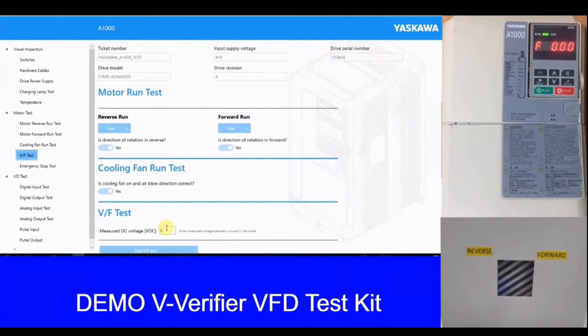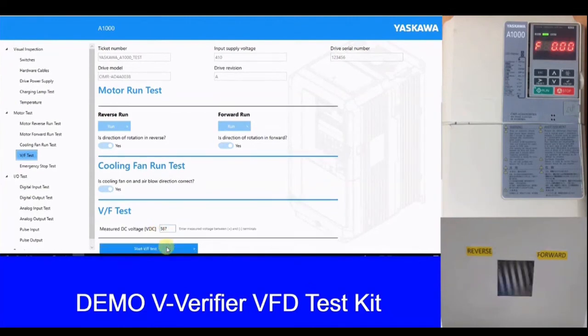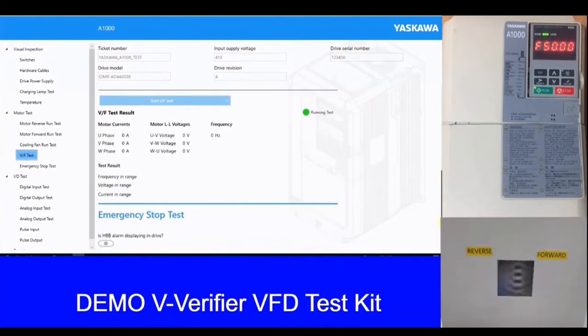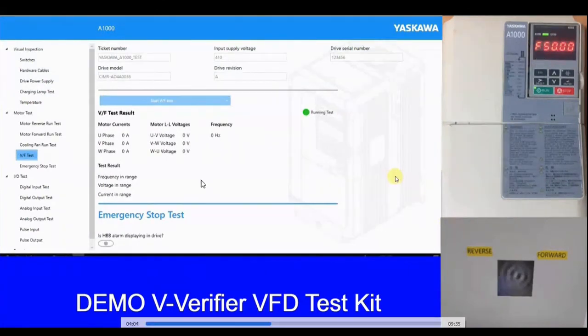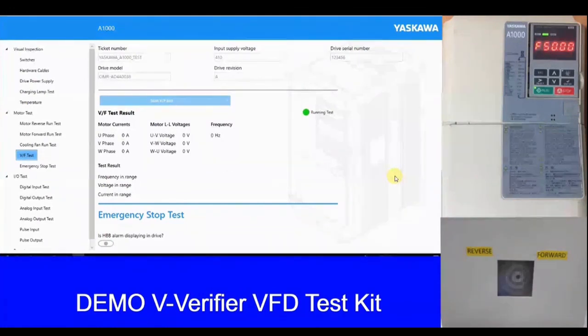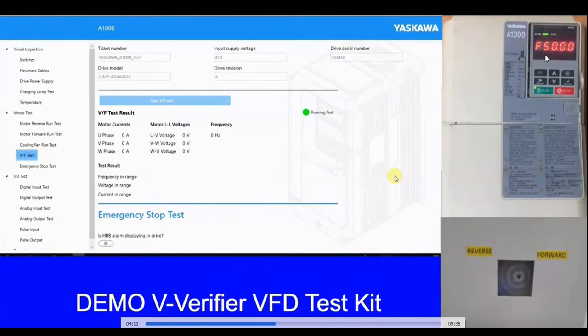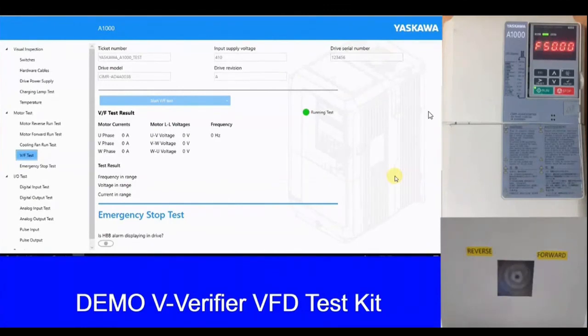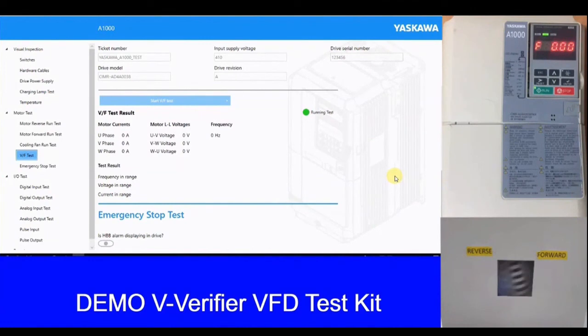Next we have the physical verification of the DC bus voltage at the terminal of the VFD. Once we enter the DC bus voltage, we start the V/F test. In this V/F test, the motor will rotate at 50 Hz, as seen on the display of the VFD, and it will run in forward as well as reverse — changing direction multiple times, roughly six times — to ensure that the current distribution and voltage distribution are balanced across all three phases and there is no problem in the IGBT firing.